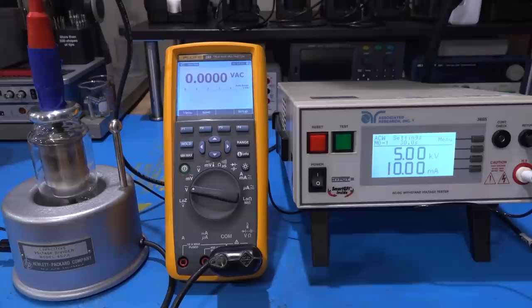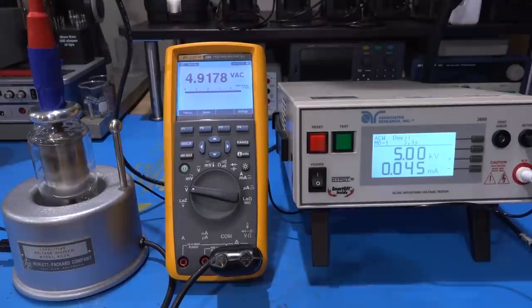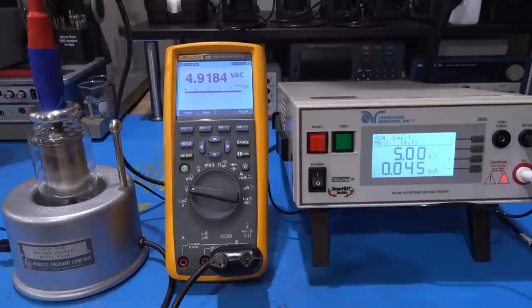Here we are at five kilovolts. Let's go and turn this on now. What do we get? 4.91. Not bad. There may be some noise pickup from the microphone because this is not well insulated. Remember that there's going to be some losses in that cable—we're losing electrons in the air no matter how much we try, so there will be a lower value division at these very high voltages. But I think it works very well and I think the restoration certainly looks good. I'm happy to add this to the lab as a weird instrument. It's certainly not something you'll be using all the time, but I still think it's a pretty cool combination of instruments to test it out.